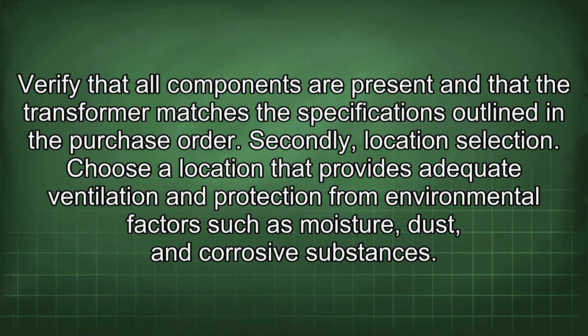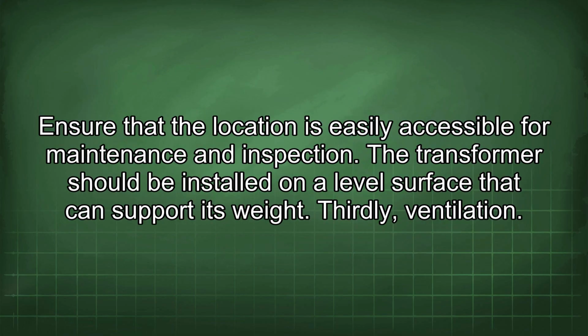Secondly, location selection. Choose a location that provides adequate ventilation and protection from environmental factors such as moisture, dust, and corrosive substances. Ensure that the location is easily accessible for maintenance and inspection. The transformer should be installed on a level surface that can support its weight.